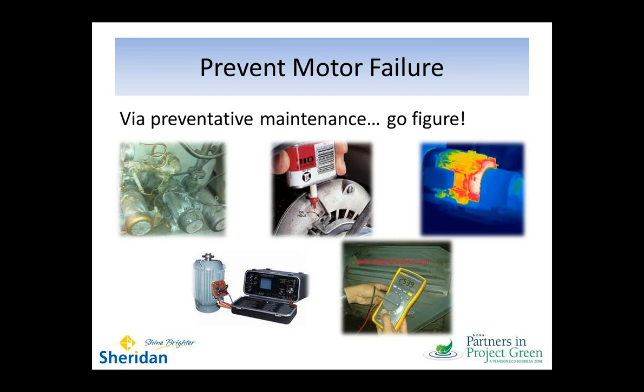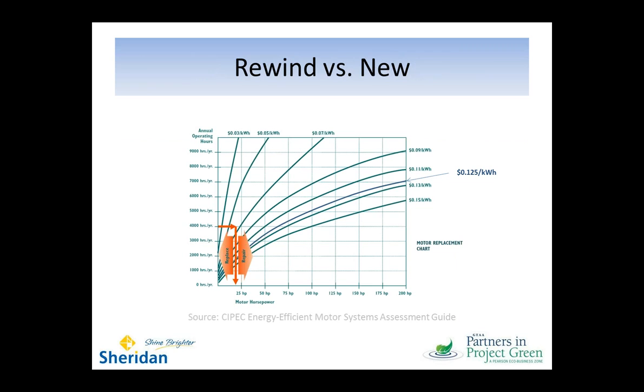So here are some of the standard things. Look at the environment, make sure there's regular lubrication of bearings and rotating parts, look for excessive heating and misalignment, measure phase voltages, and measure resistance of insulation. And ultimately, when you're doing motor management planning, you're going to come to this consideration of whether you send the thing out to repair or whether you try to replace it.